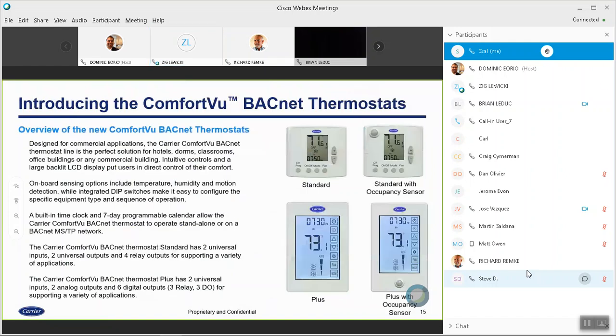Okay, quickly switching gears to the ComfortVu stats. The biggest difference between these thermostats and the Connect stat is that they basically have additional or different types of output capability. The standard versions, the ones you see at the top, come in two tiers. They have two universal inputs, two universal outputs, and four relays for a variety of applications that you may use. On the Plus version, you have two universal inputs and two analog outputs with six digital outputs.